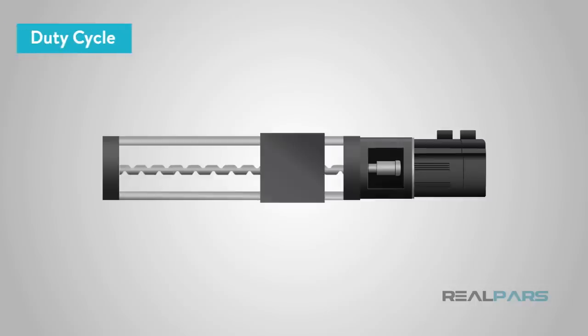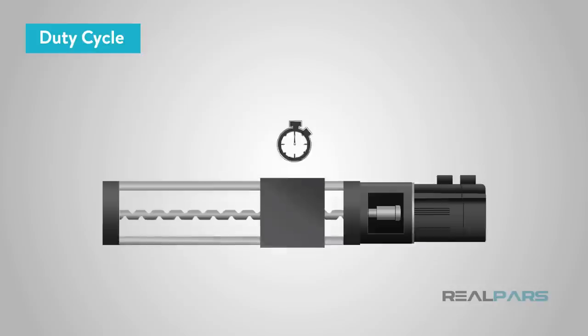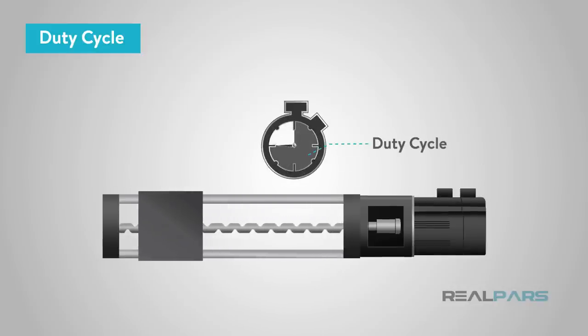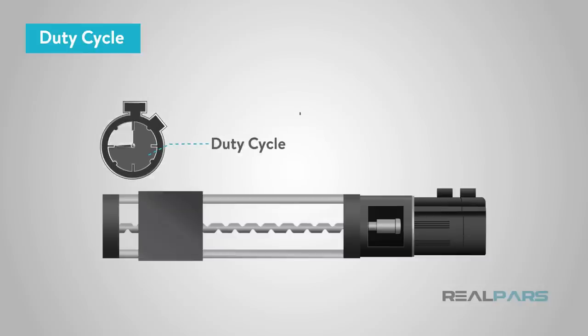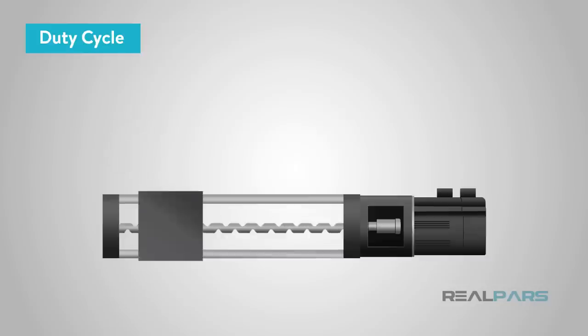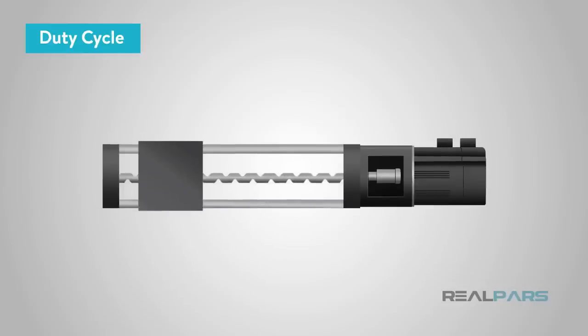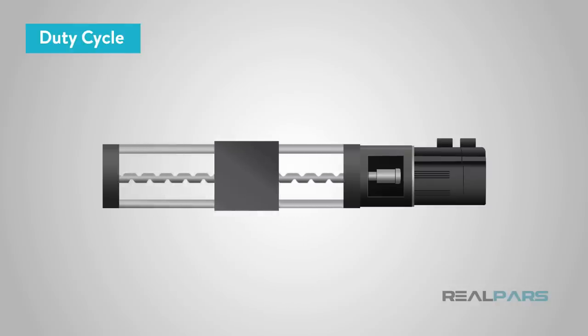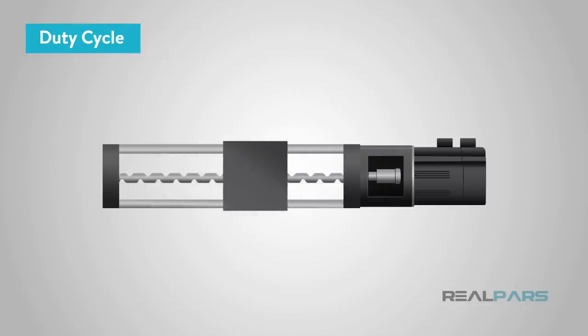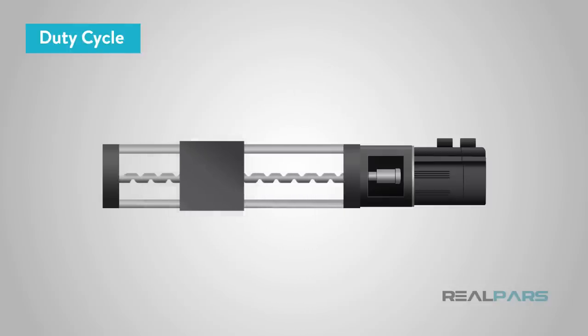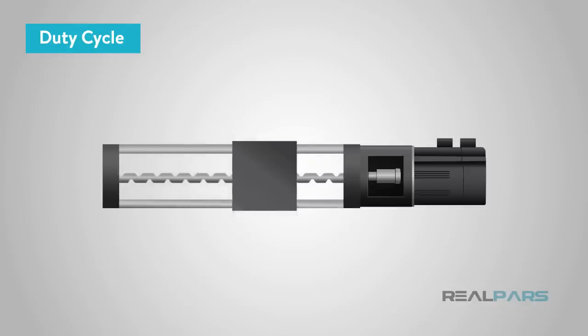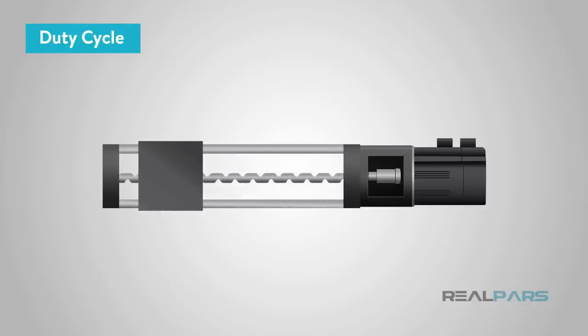In addition, you will need to determine lifetime requirements or the duty cycle. Duty cycle is defined in how often the actuator will operate and how much time will elapse between movements. Duty cycle is based on the number of expected repetitions per unit of time in hours per day, minutes per hour, and or strokes per minute. Cycle times determine the life of a linear motion control system. The repetitive motion of back and forth or up and down movements produces friction, and this friction creates wear and tear on the system components. This cycle time or duty cycle is critical criteria in determining the operating life on just how long you want your system's investment to last.